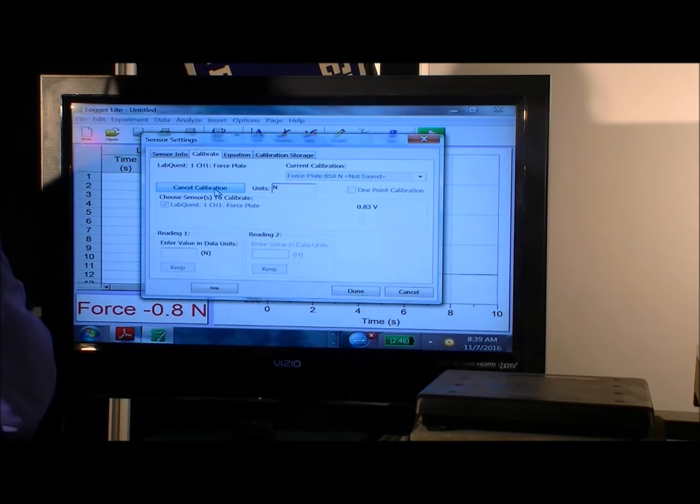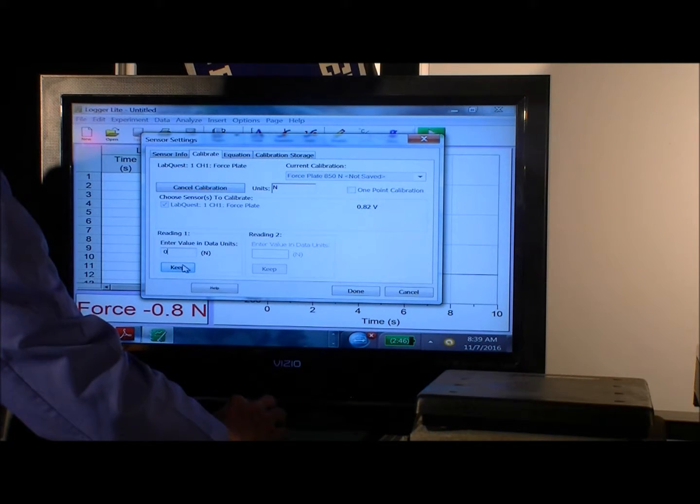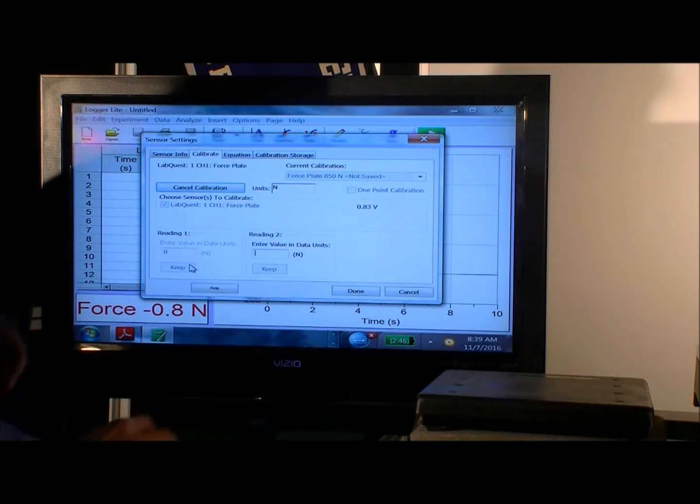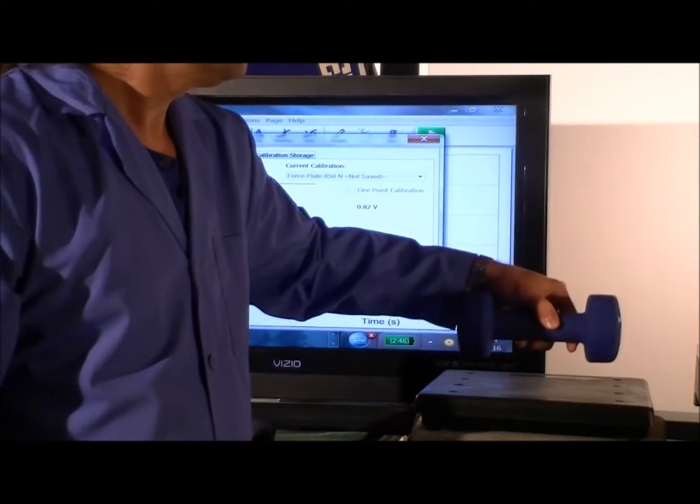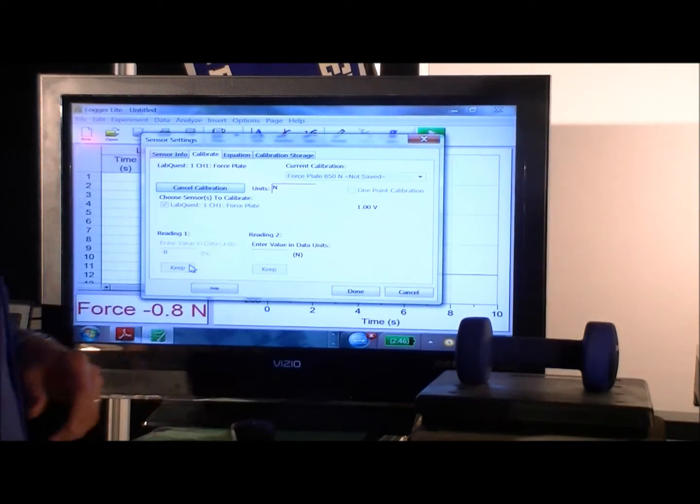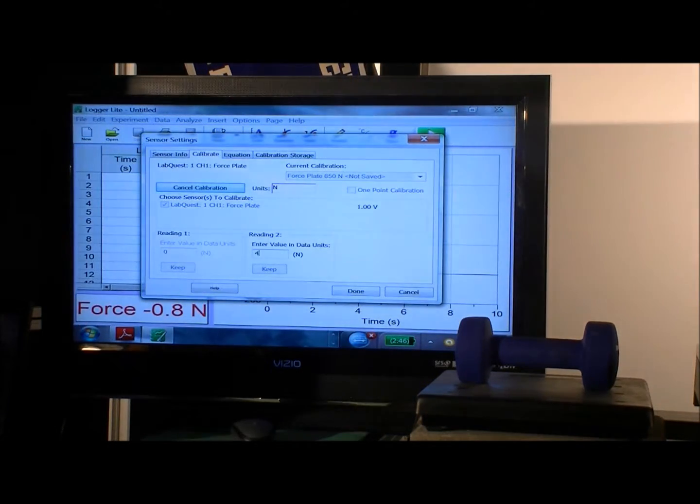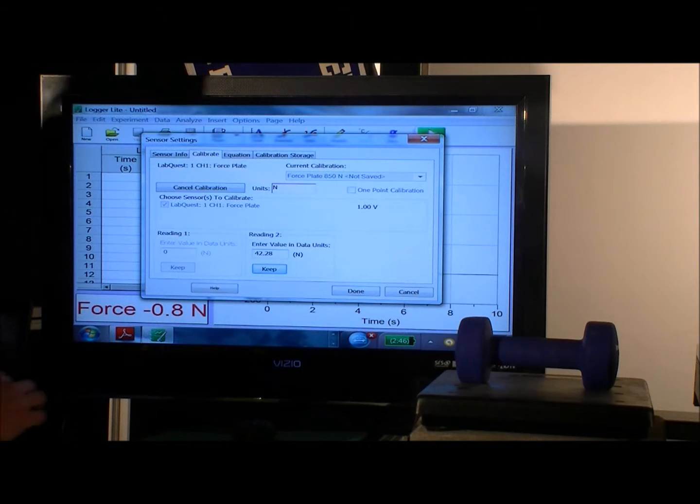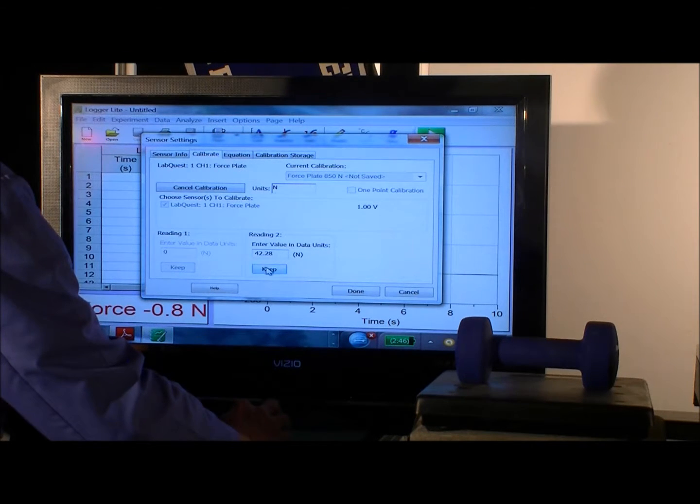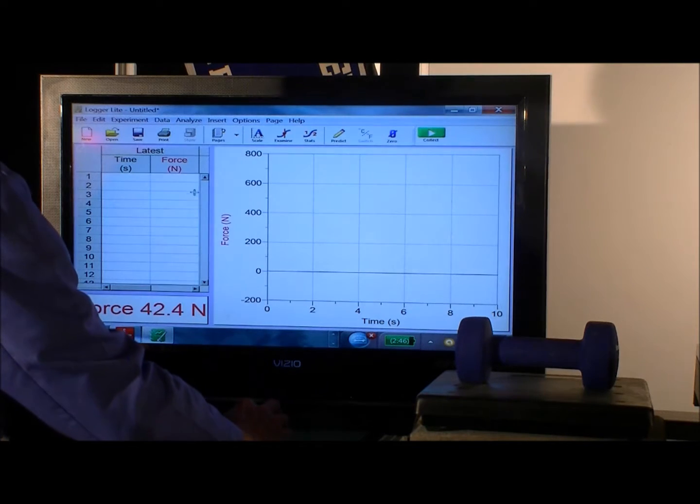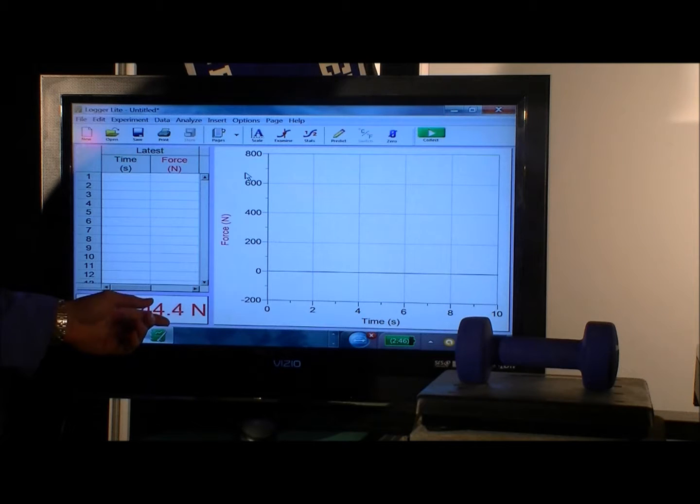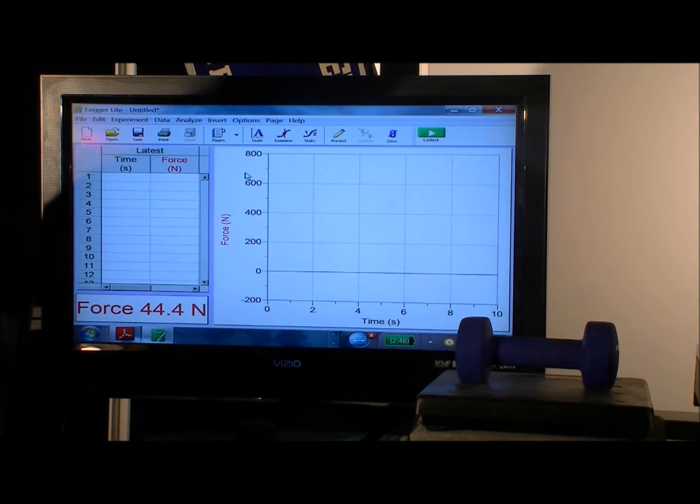Now in Newtons, and right now there's nothing sitting on the force plate, so we enter a zero Newtons because we know that the force applied on the force plate right now is zero Newtons. And then we put the 10 pound weight up there, and we put our 42.28 Newtons that we know corresponds to our 10 pound weight. We hit keep, then we hit done.